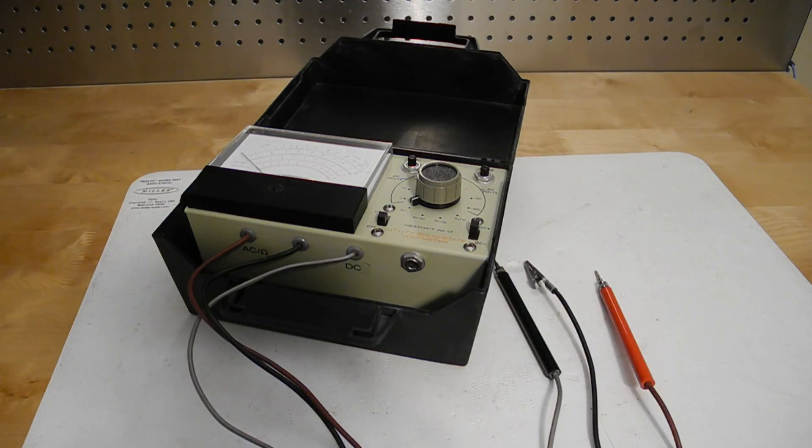The resistance ranges are not calibrated. You just verify that the ohms adjust control works correctly. I tested against a number of resistance values using a resistance substitution box and the readings were reasonably accurate.